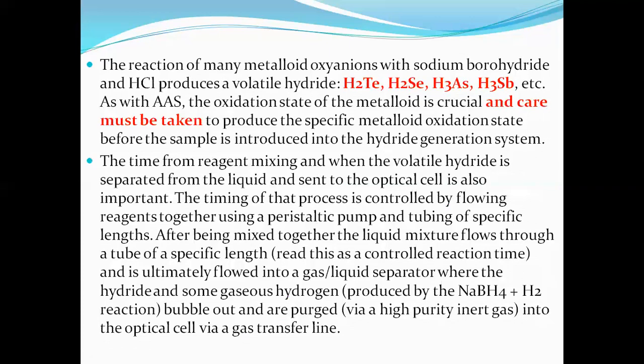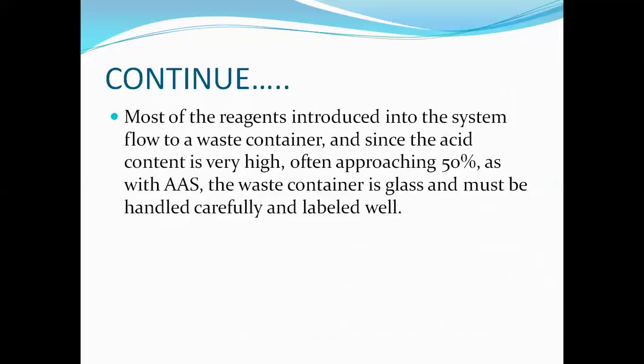After being mixed, the liquid mixture flows through a tube of specific length and into a gas-liquid separator, where the hydride and some gaseous hydrogen bubble out and are purged into the optical cell. Most reagents flow to a waste container, and since the acid content is very high — often approaching 50% — the waste container must be glass, handled carefully, and labeled well.